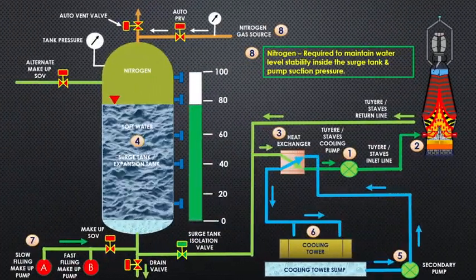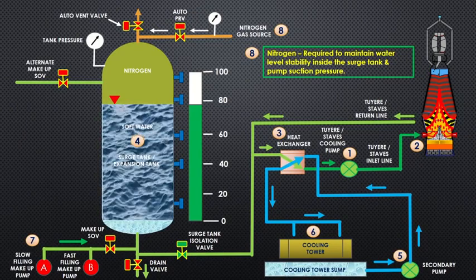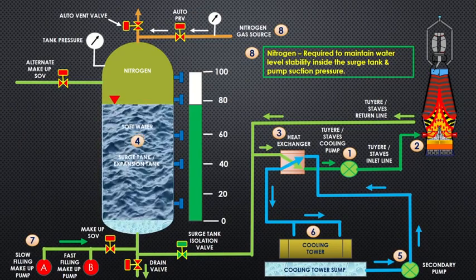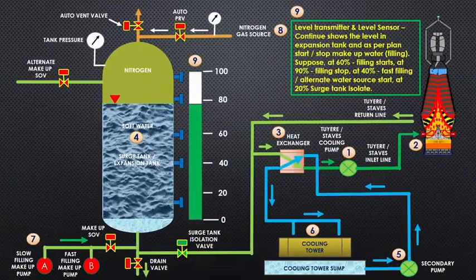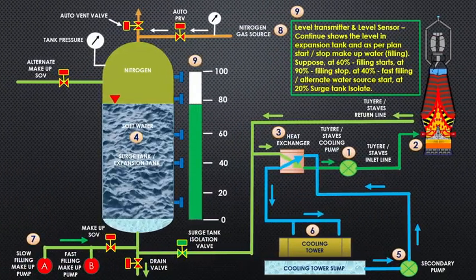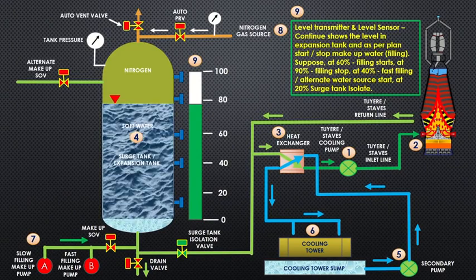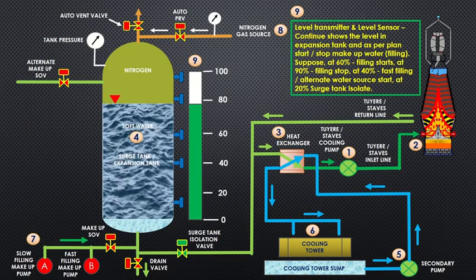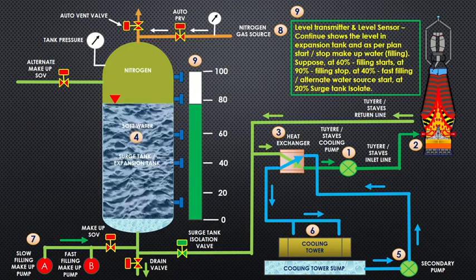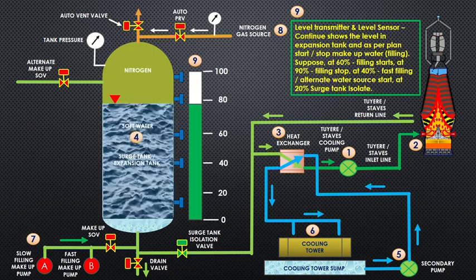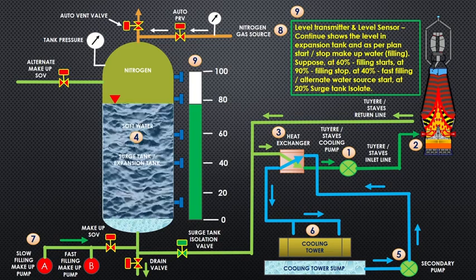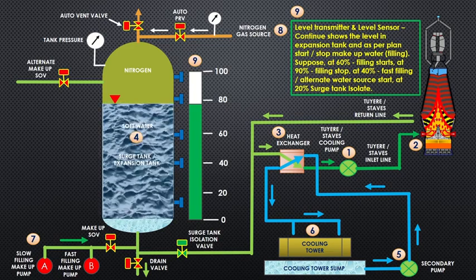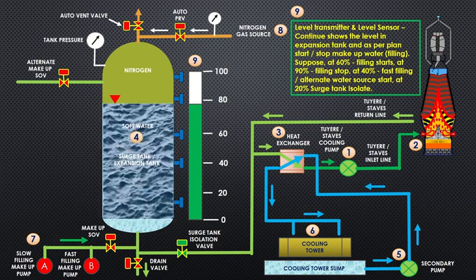Nitrogen is required to maintain water level stability inside the surge tank and pump suction pressure. Level transmitter and level sensor continuously show the level in expansion tank and as per plan start or stop makeup water filling. Suppose at 60% filling starts, at 90% filling stops, at 40% fast filling or alternate water source starts, at 20% surge tank isolates.